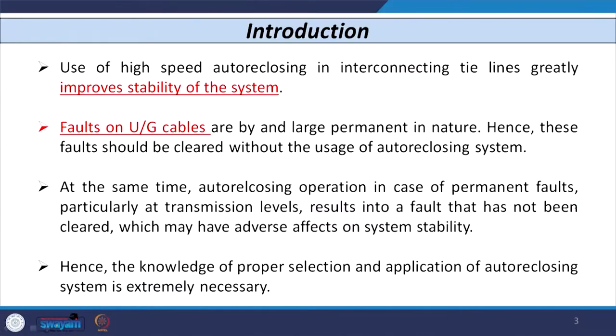Auto reclosing operation in case of permanent faults is an important concern. Since we do not know whether a fault is permanent or transient, if the fault is permanent and we use auto reclosing, that may have a bad impact on the circuit breaker contacts and in the worst case may also affect the stability of the system. Therefore, proper selection and application of auto reclosing is very important.